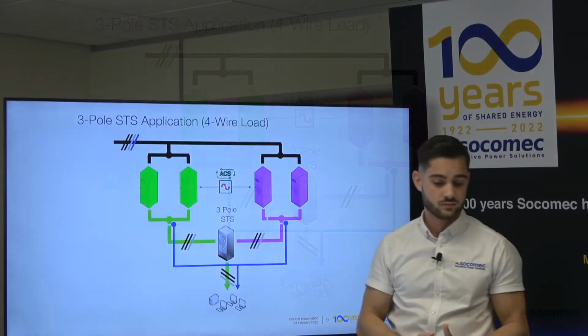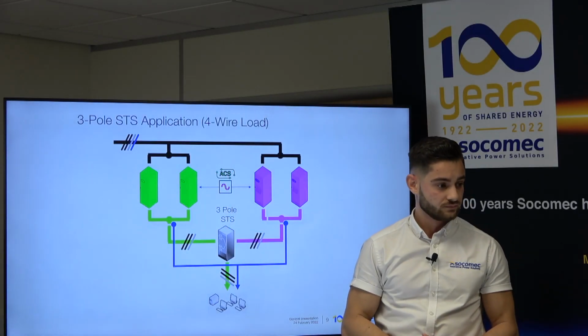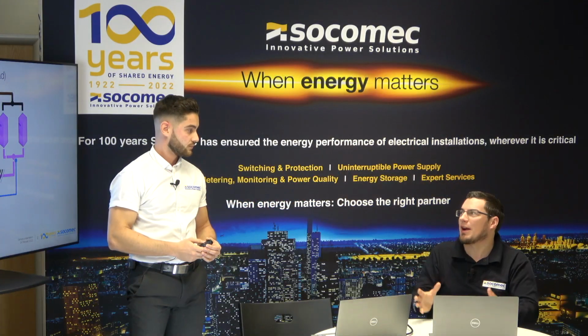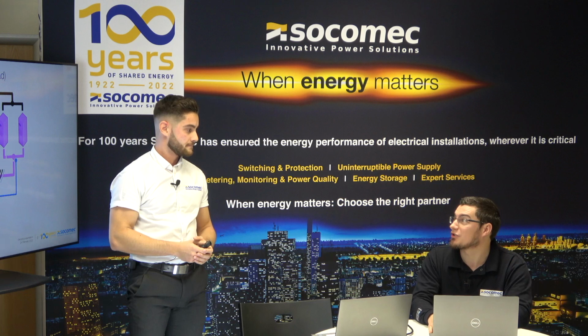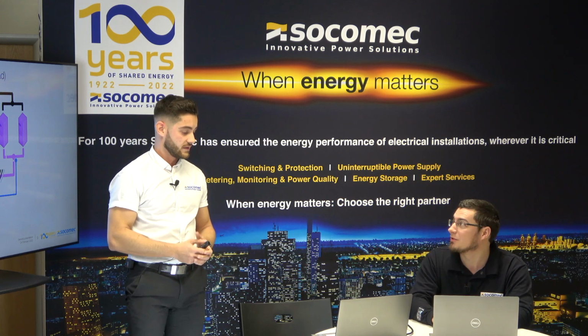Yeah, and it's important to point out that it is reconnected directly at the STS input side, so it's taken in and taken back out to your load. So if in the future you changed and wanted to split that system, you may have to look at adjusting the STS to suit the application better. Yeah, absolutely.